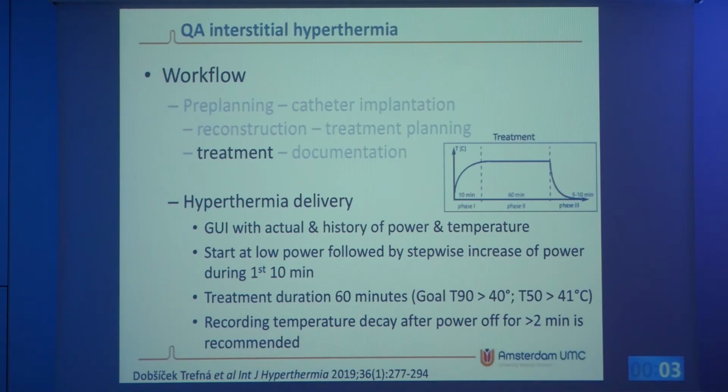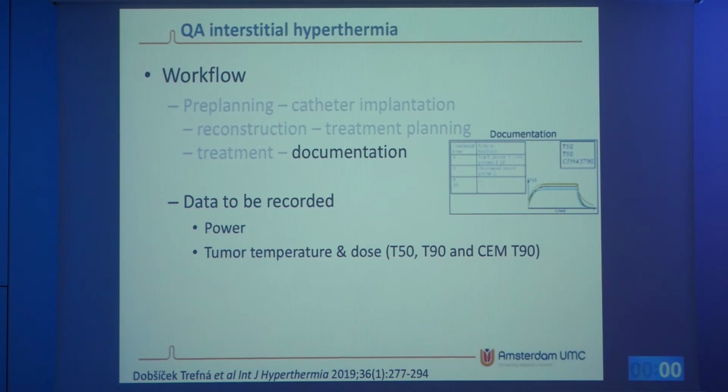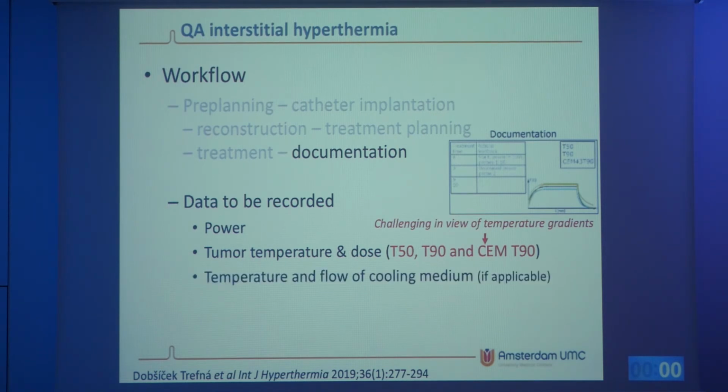And after the end of treatment, you should still measure the temperature for some time in order to see what the temperature fall-off is within that period. So that's the documentation, and the data to be recorded are power, temperature, and it's very important also to look at the cumulative dose.